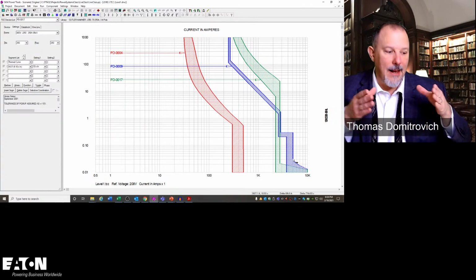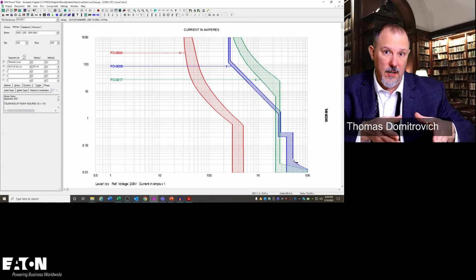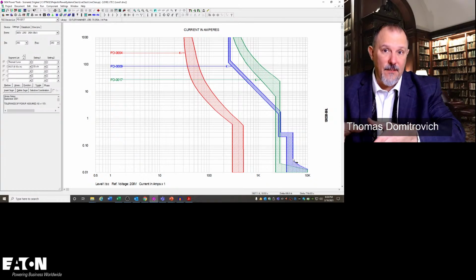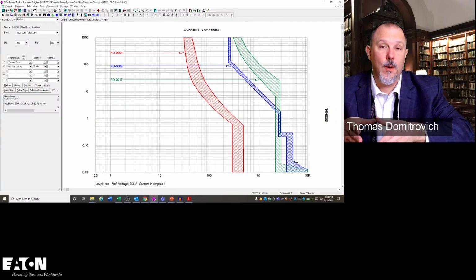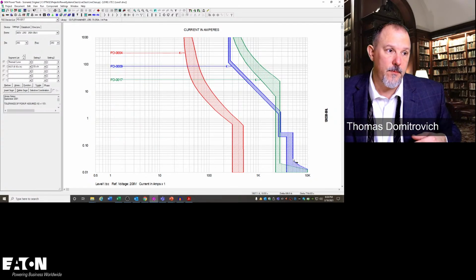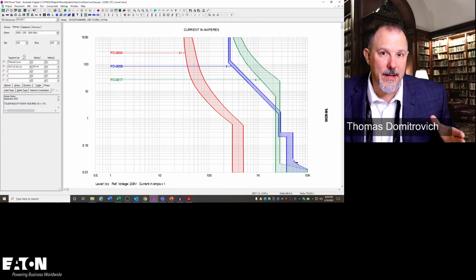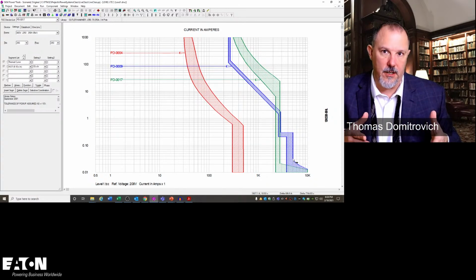But when you're talking life safety, Article 700, 708, 701, now it makes a difference. And that's why those articles have elected to go to selective coordination. But outside of the requirement, it's really a design decision.